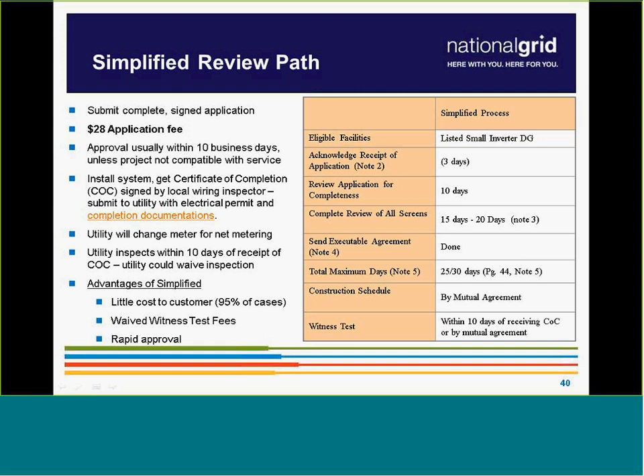So once we see that information, your utility, once we see that certificate of completion, and if we choose to waive it, which we do the majority of the time, then we would install the requested bidirectional meter. Once the bidirectional meter has been installed and you verify the count is recorded correctly, then you get your authority to connect. This is for the simplified process.